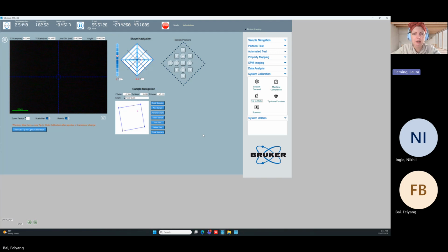So good. And then my final question to you is, usually the question is, do I have an accurate tip area function? For scratch, do I need one is the question. And what that question is really asking is, what does the tip area function give me again? The tip area function. I think the tip area function gives us a good beginning reading of where 0 is. Rezeroing is necessary on all data files. That is not the same thing. It was part of us performing the tip area function calibration, but those are two separate steps.